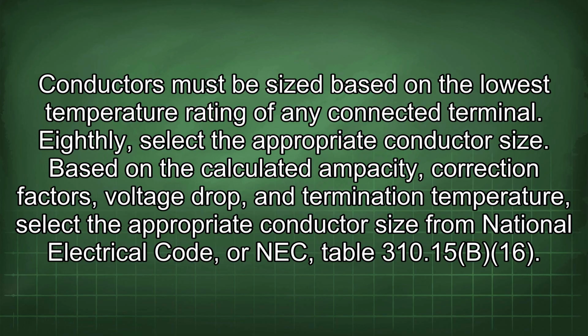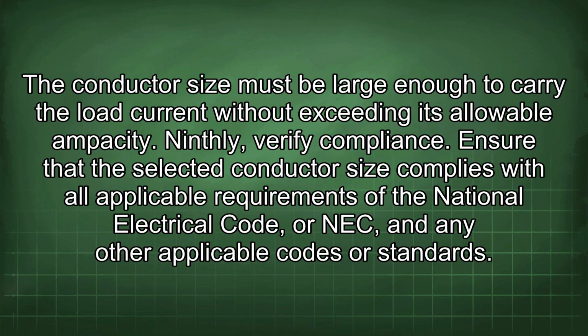Eighthly, select the appropriate conductor size. Based on the calculated ampacity, correction factors, voltage drop, and termination temperature, select the appropriate conductor size from NEC Table 310.15(B)(16). The conductor size must be large enough to carry the load current without exceeding its allowable ampacity. Ninthly, verify compliance. Ensure that the selected conductor size complies with all applicable requirements of the NEC, and any other applicable codes or standards.